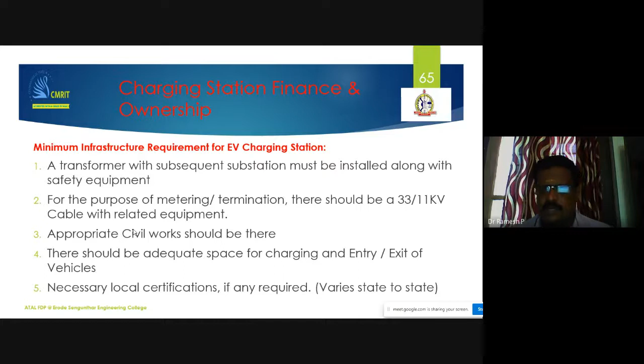So what are the minimum infrastructure requirements for an EV charging station? A transformer with a subsequent substation - a 250 kVA transformer is required along with safety requirements. Also, for the purpose of metering termination, there should be a 33 by 11 kV cable with related equipment. Appropriate civil work should be there, adequate space for charging and entry or exit of vehicles, and necessary local certification based upon state norms.